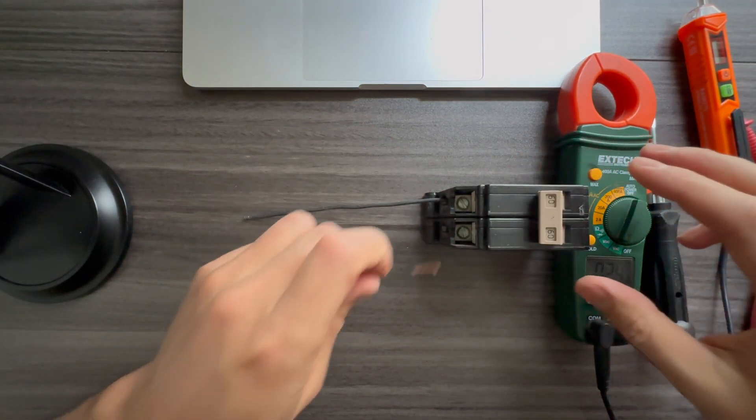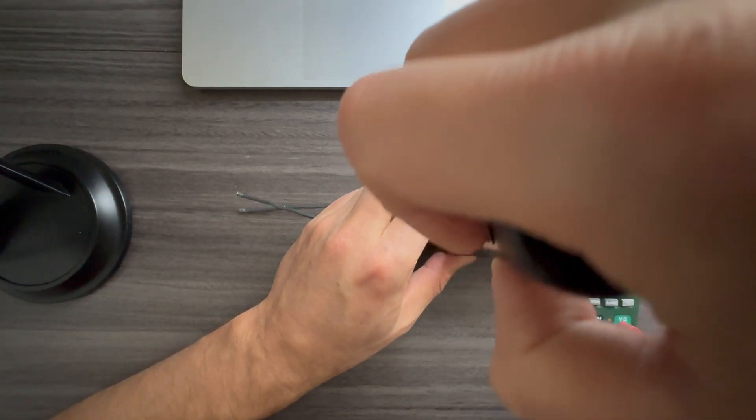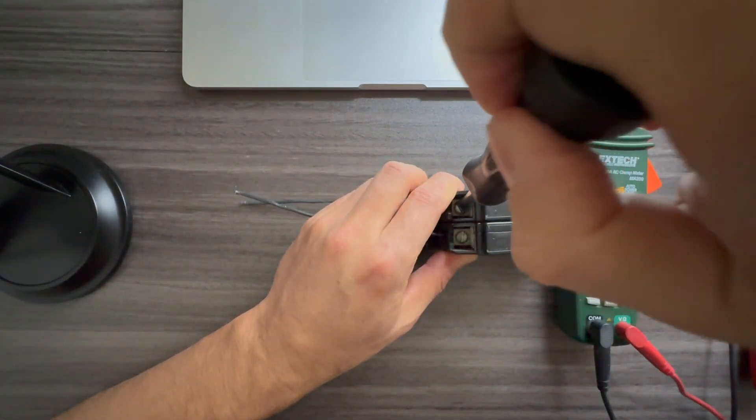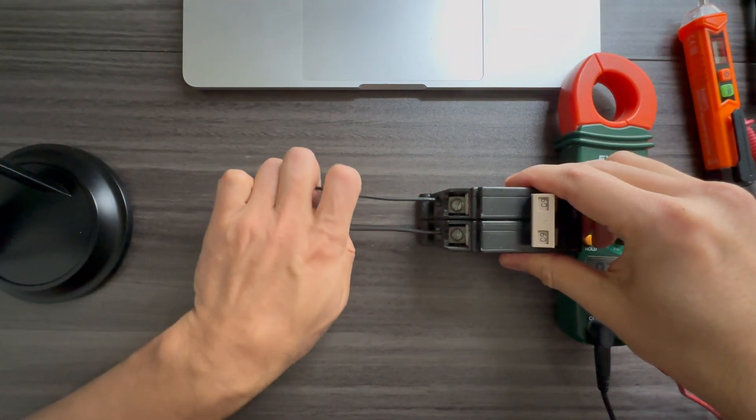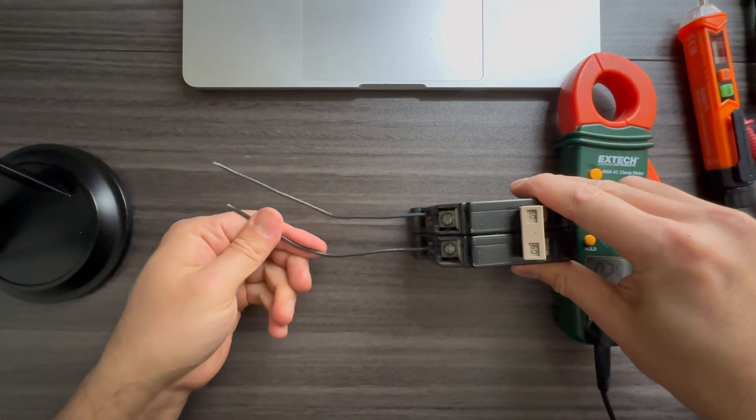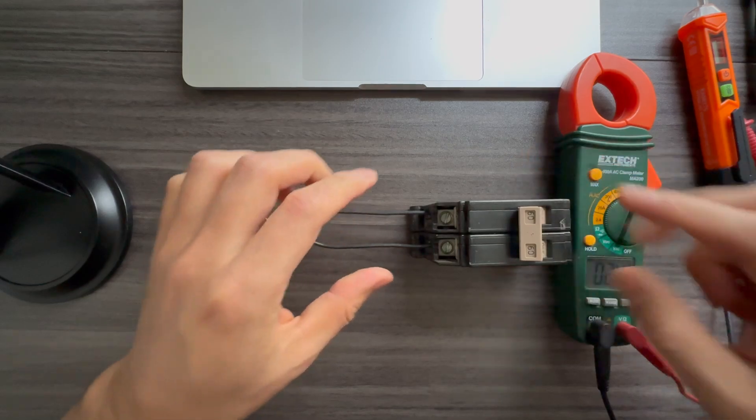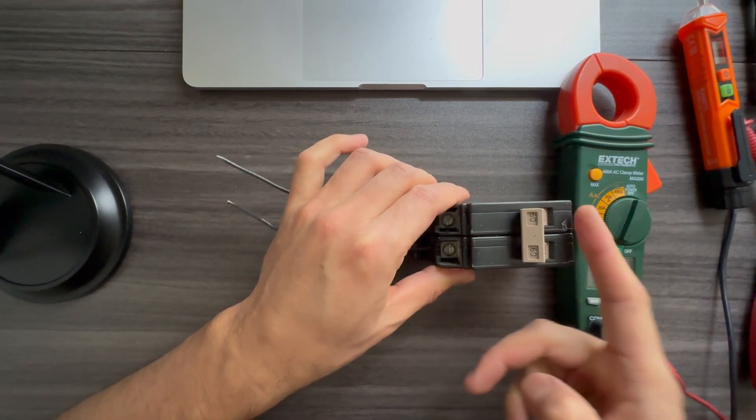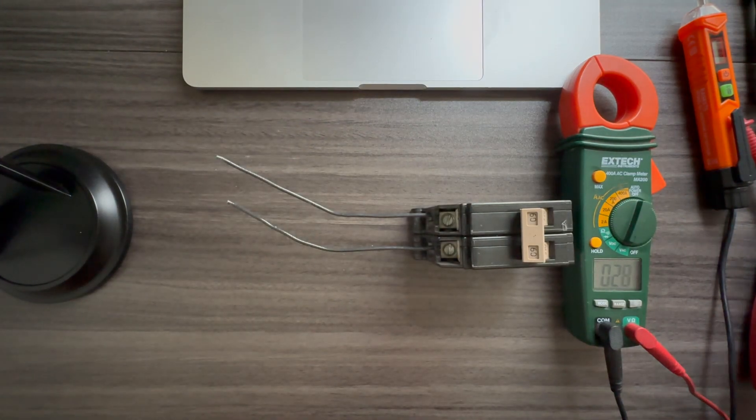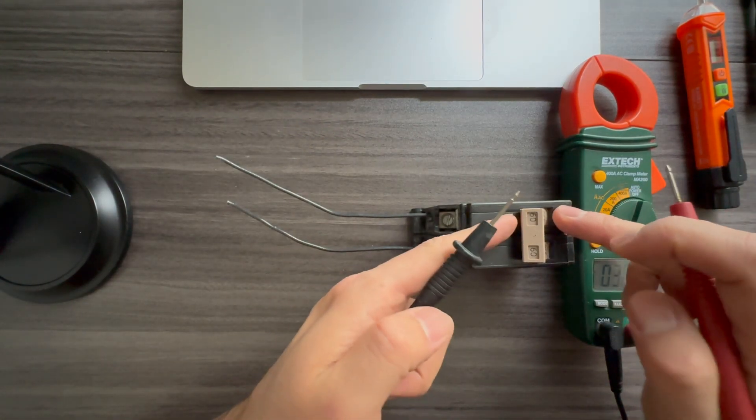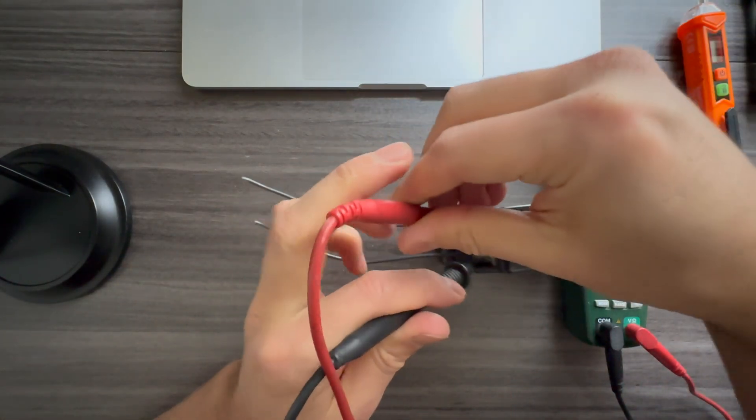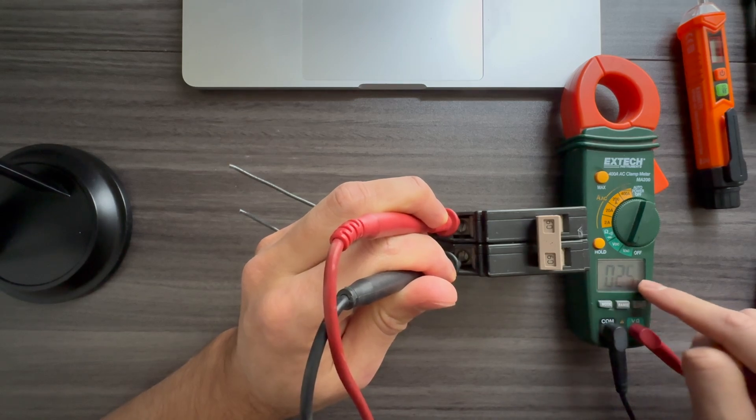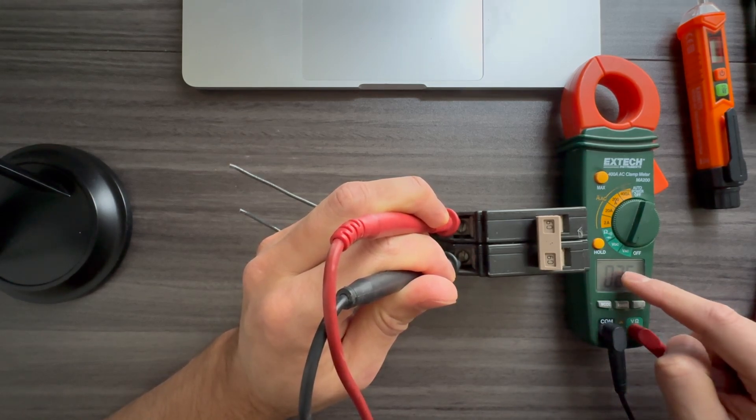And then another step, right. So you have a breaker that comes on, it is on, but you don't know if it's working, but nothing's working. So let's say in this case, I just pulled it out from a customer's place. That's why I'm making it. She wasn't sure if it's a short or not. So let's say if it turns on, it is staying on, but you don't have power. Again, we're going to need a voltmeter. While this thing is on, if it's a double pole, we're going to measure these two terminals to see if we have 240 volts here.